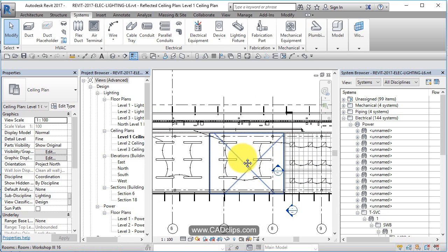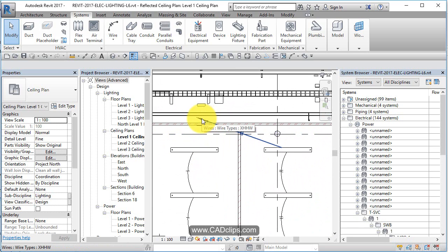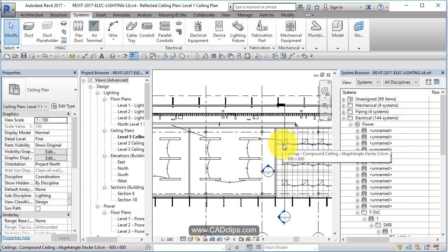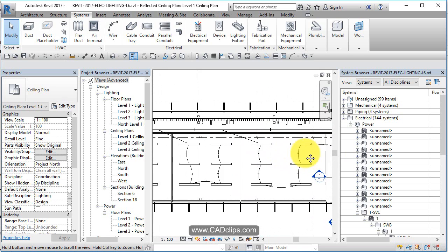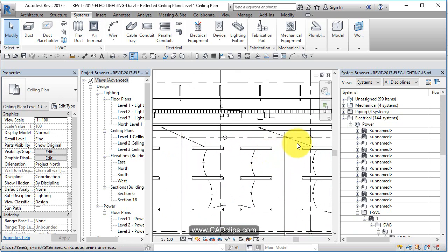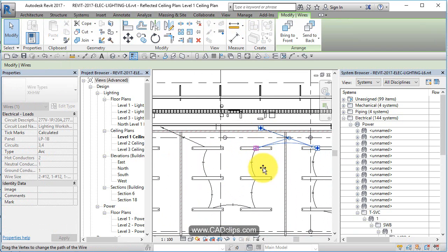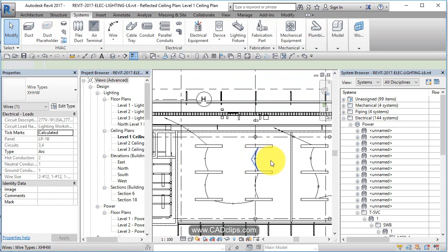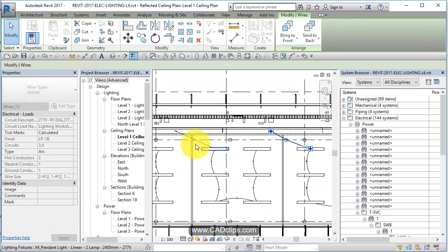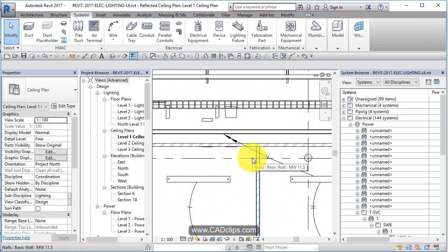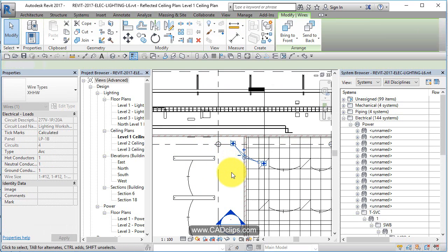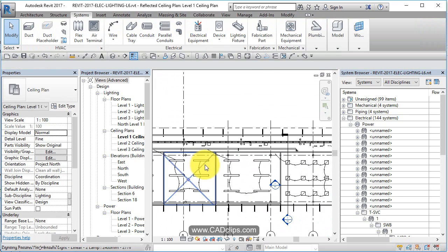As you work with wiring, you'll notice arrowheads on your home run don't always correspond to what you think are the circuits. Sometimes there are phantom circuits buried in that aren't tied to anything, so you almost have to go through each device and purge them out. For example, dragging one wire set to connect with others gives that home run three arrowheads and more hot conductors. Pulling it back out returns them all to one arrowhead each.